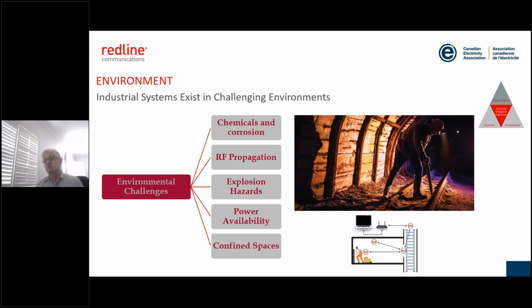As I mentioned, the existence of chemicals introduces explosion hazards. There's also power availability. It's not always possible to provide 48 volt DC to the communication infrastructure everywhere in a power system or in a mine. Voltage levels vary - a relay building system might be 250 volts DC or 125 volts DC, while in mining you may have a 24 volt DC system.